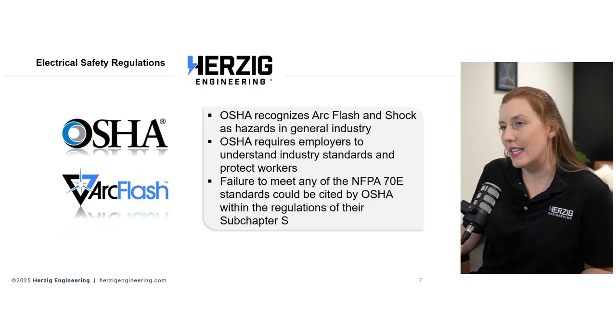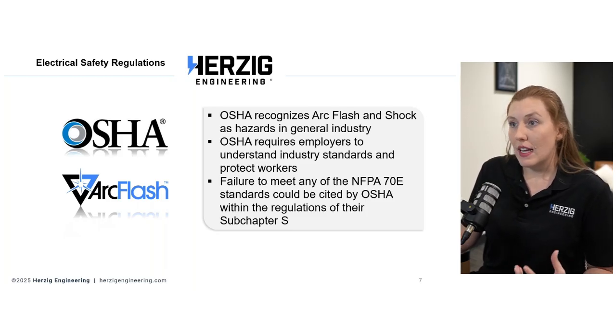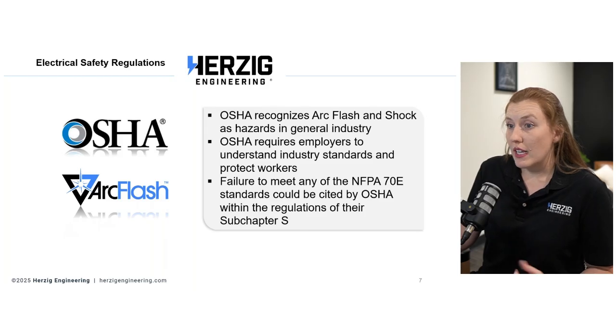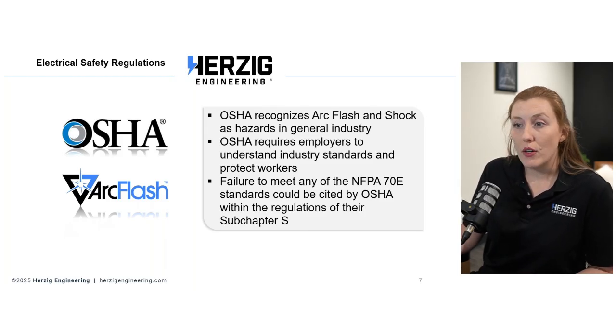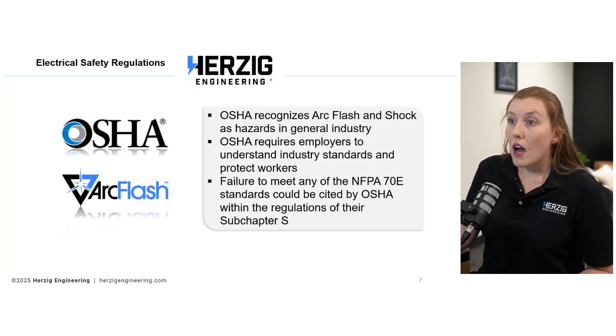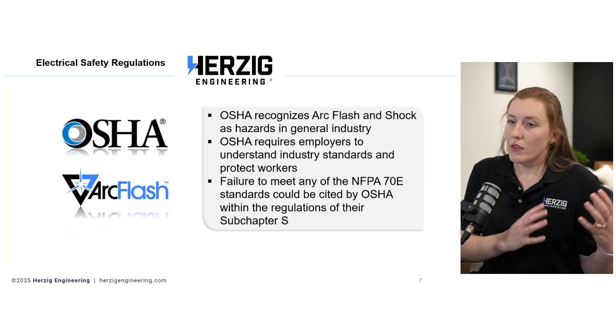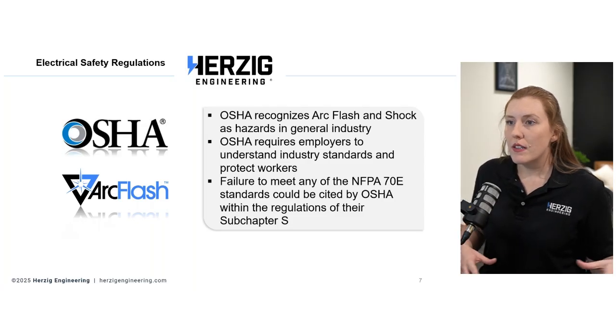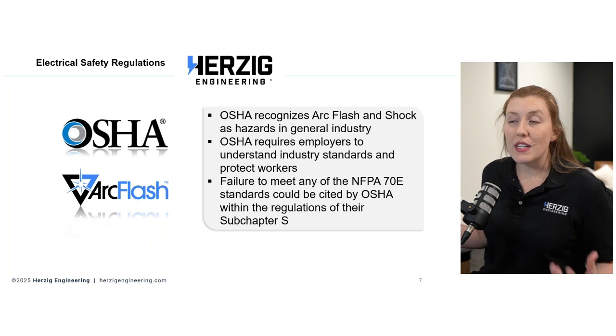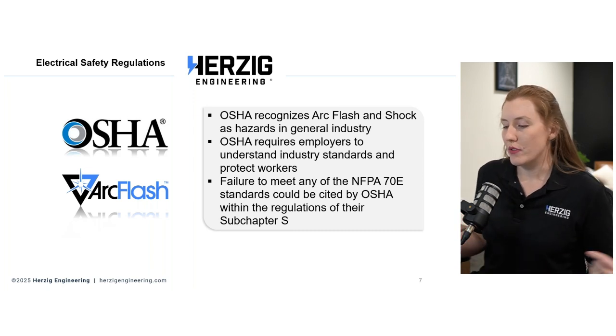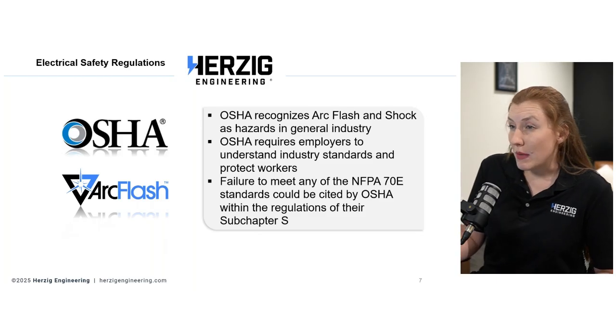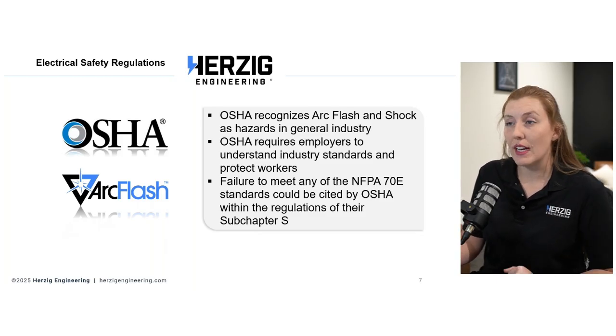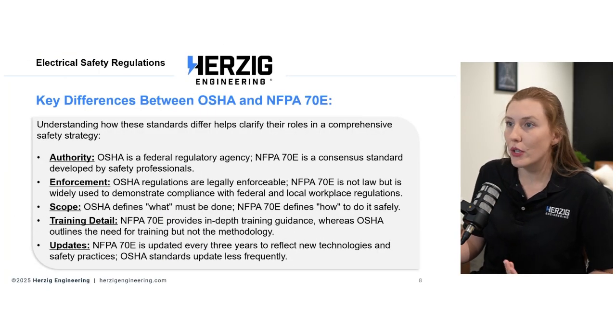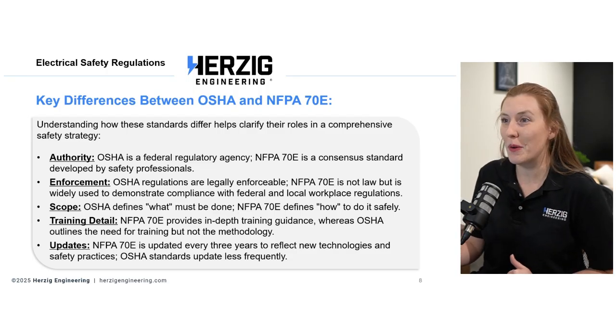That's where the NFPA 70E comes in. It is considered the recognized industry consensus standard, so failure to meet the NFPA 70E standards could actually be cited by OSHA within the regulations of their subchapter S under the general duty clause. So the OSHA regulations are the bare minimum requirements, and the 70E gives you more than enough guidance on how to comply with those bare minimum requirements. If you don't at least meet what's out there as far as recognized standards, and something goes wrong, OSHA can use those recognized standards to support their citations - as an example, saying you could have protected them because here's a million ways you could have.